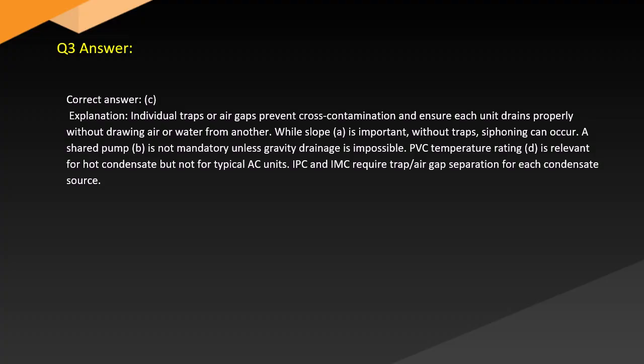Answer. Correct answer: C. Explanation. Individual traps or air gaps prevent cross-contamination and ensure each unit drains properly without drawing air or water from another, while slope (A) is important. Without traps, siphoning can occur. A shared pump (B) is not mandatory unless gravity drainage is impossible. PVC temperature rating (D) is relevant for hot condensate but not for typical AC units. IPC and IMC require trap or air gap separation for each condensate source.